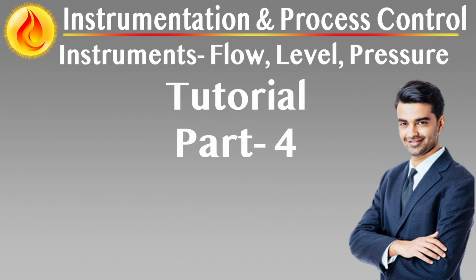Impulse line design and configuration. Impulse lines connecting the transmitter to the process tappings must be short and of equal length to minimize lag and imbalance, sloped and self-draining for gas service or free of gas pockets for liquid service, equipped with block, vent, and drain valves for isolation, calibration, and maintenance. In viscous, dirty, or hazardous services, impulse lines may require heat tracing, purging, or diaphragm seals to maintain operability and prevent plugging or freezing.